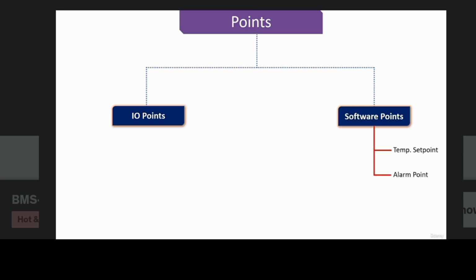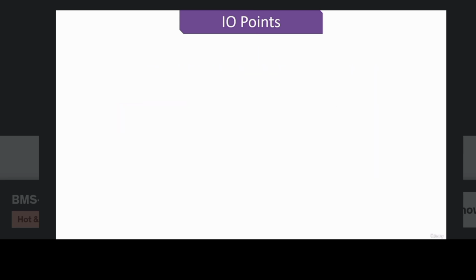Another example of a software point is an alarm point. These types of points are created inside the software for indication of alarms. For example, a fan failure alarm can be generated if the belt of your AHU fan is broken. Now we will discuss IO points in more detail.